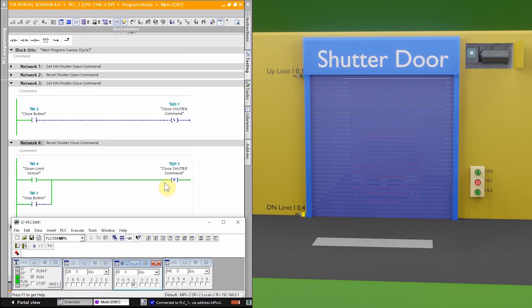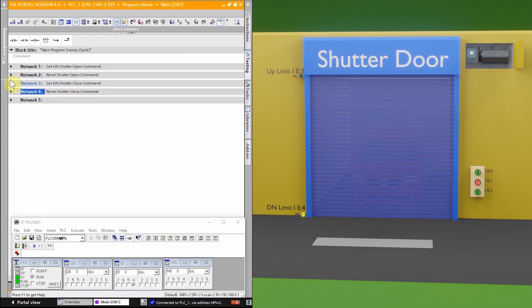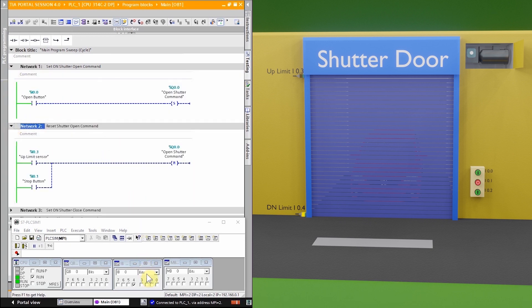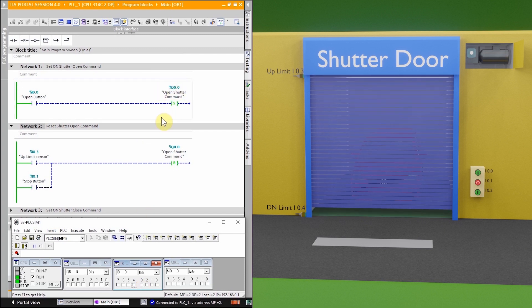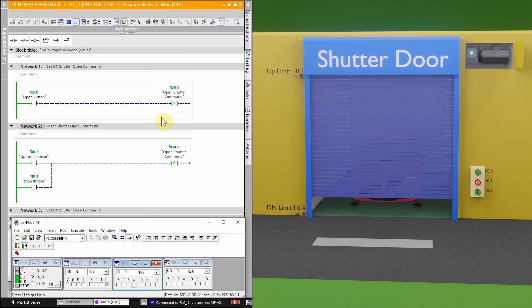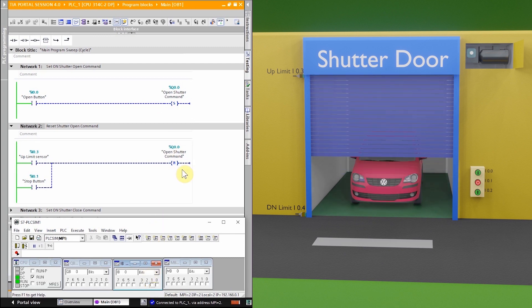Next, let's test stopping the shutter motor at a mid position. We go to networks one and two, press the open push button, which sets output Q0.0, and the shutter starts opening. At any intermediate position, if we press the stop push button I0.1, it resets output Q0.0 and the shutter motor stops at that position.